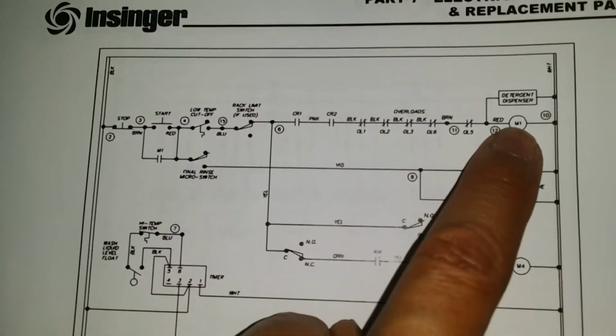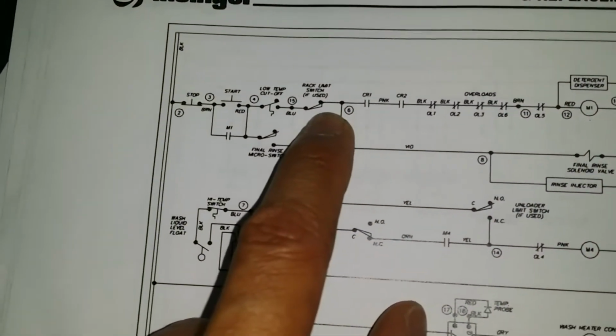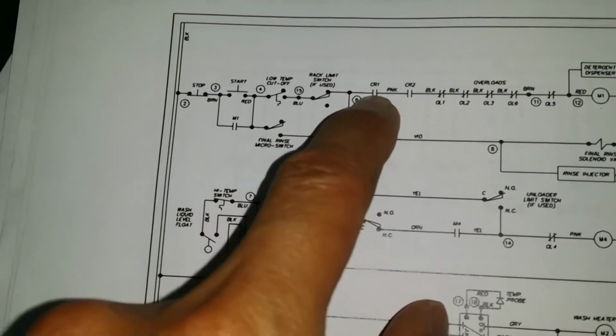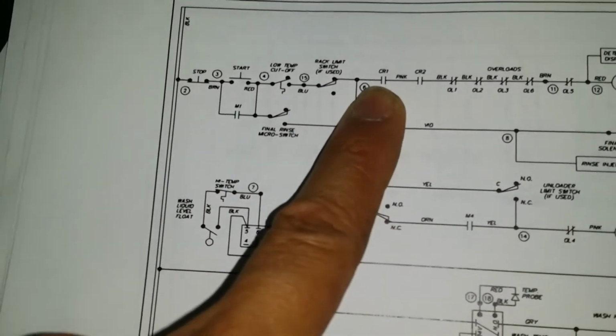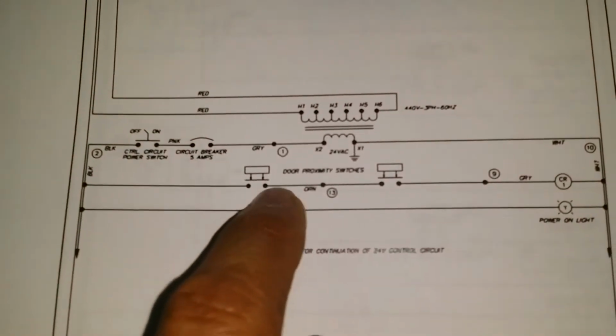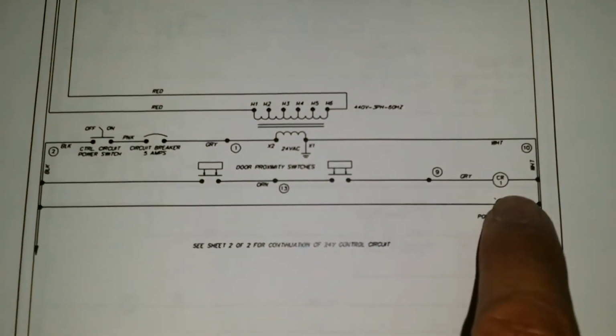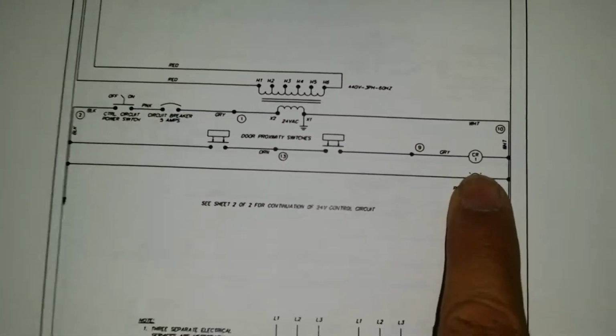To energize the main contactor, we have to meet a lot of permissives. Some of them are CR1. CR1 means that the doors are closed. And this is what I mean: if these two are closed, this relay should energize. And by the way, these relays are here.